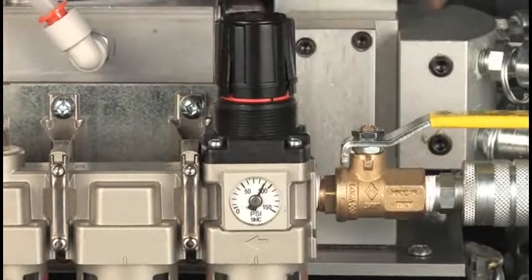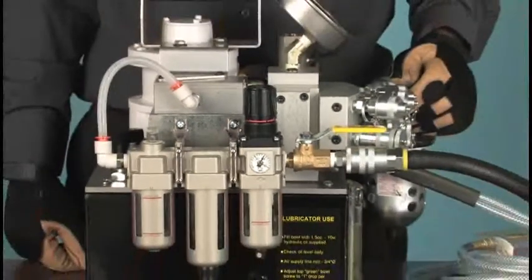The speed of the pump depends not just on the pressure, but on the volume of air supplied. For best operation, the pump requires 40 to 50 cubic feet per minute through at least a three-quarter inch supply hose.